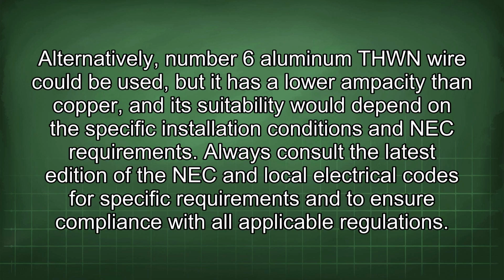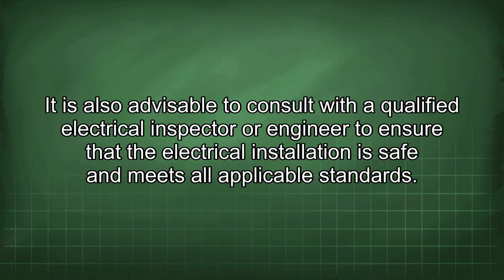Alternatively, number 6 aluminum THWN wire could be used, but it has a lower ampacity than copper, and its suitability would depend on the specific installation conditions and NEC requirements. Always consult the latest edition of the NEC and local electrical codes for specific requirements and to ensure compliance with all applicable regulations. It is also advisable to consult with a qualified electrical inspector or engineer to ensure that the electrical installation is safe and meets all applicable standards.